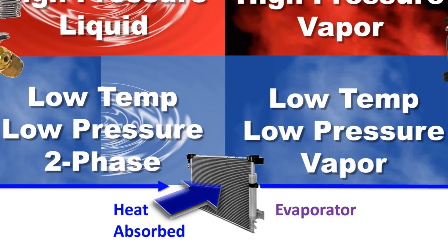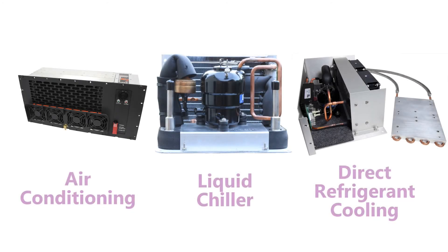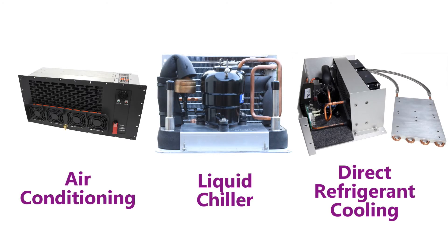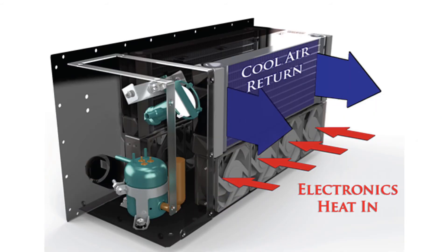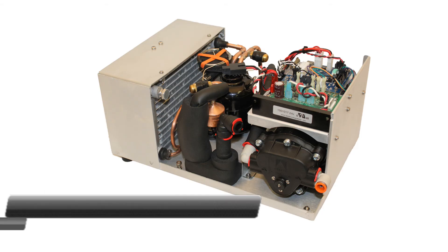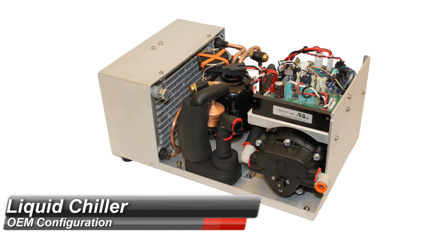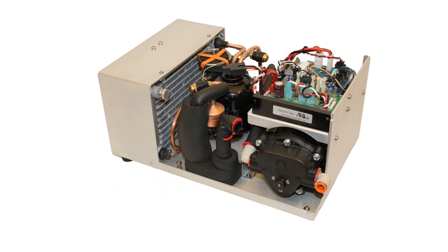By varying the evaporator, the vapor compression cycle can be used to cool air, liquid, or cold plates. To create an air cooling system, the evaporator is a refrigerant to air heat exchanger. To cool liquids, the evaporator is a refrigerant to liquid heat exchanger, with the pumped liquid being cooled by the evaporating refrigerant.